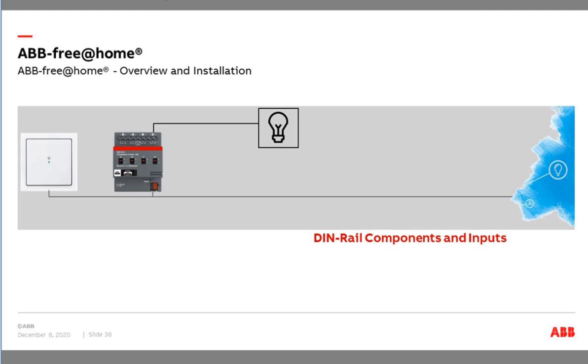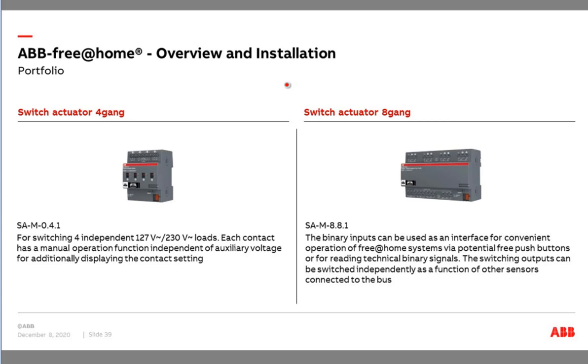The last part of the components are the DIN rail components and the inputs. Starting with switching actuators: we have two different types. One is a simple switching actuator with four channels with the possibility for manual operation directly on the device. The second is a switching actuator with eight outputs — and this is again a combination device, because it also has eight binary inputs at the same time. So when you want to add conventional switches or signals from a window contact, you have a good combination device with both switching actuator and binary input integrated.